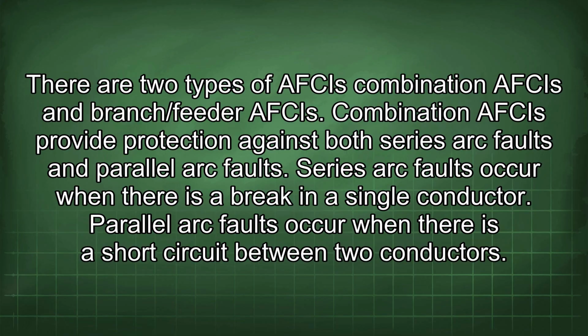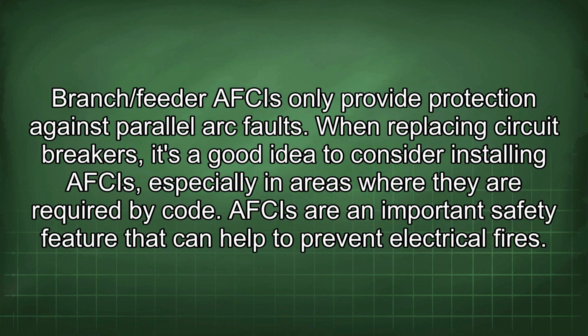There are two types of AFCIs: combination AFCIs and branch/feeder AFCIs. Combination AFCIs provide protection against both series arc faults and parallel arc faults. Series arc faults occur when there is a break in a single conductor. Parallel arc faults occur when there is a short circuit between two conductors. Branch/feeder AFCIs only provide protection against parallel arc faults.